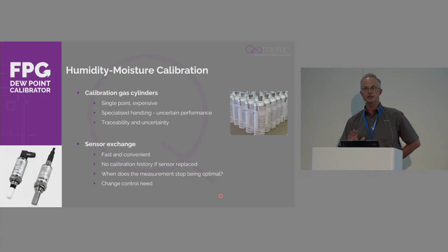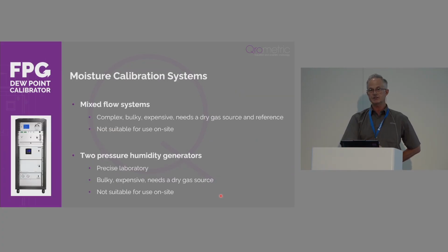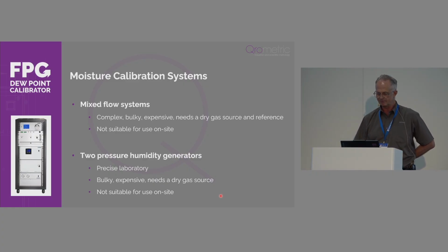Another very good way of doing it is to do a sensor exchange, which means that you take the sensor out and you replace it with one that you know is good, which is very convenient, very practical. The problem is you don't really quite know when the sensor stopped being good or when the sensor has had a problem. So you never really know whether the measurement is correct.